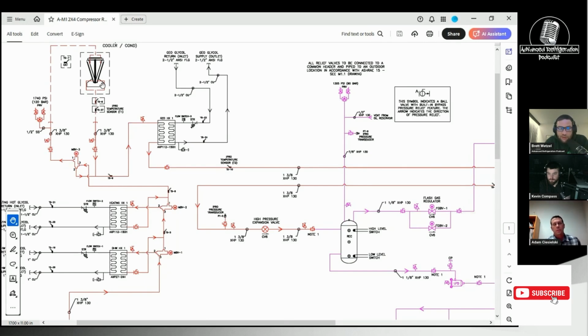What does that do for the density? I'm not a chemical engineer or a mechanical engineer, so I'm curious what that actually does for the density. Does a supercritical fluid get more dense? Does it take a larger capacity when you have those states of that refrigerant? Yeah, it is liquid. So the density from a liquid perspective is going to be more constant as compared to if you increase the pressure for a vapor, but the density still does increase if you're running 733 pounds with 60-degree liquid compared to 60-degree liquid with 1,200 psi. So I'm sorry, you say the density would increase at that higher pressure? It does. Yes, it does increase.